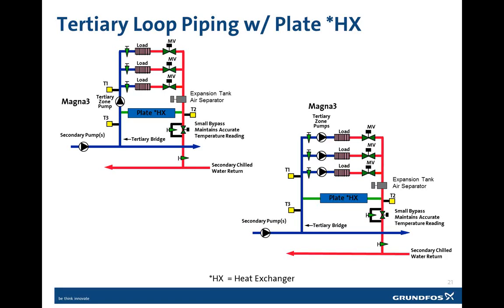So a plate heat exchanger acts as a pressure isolator. If you consider a multiple building campus with a central plant, there could be blocks or miles from the first takeoff all the way out to the farther zone. The near building may be a one-story multi-office building, which requires about 20 feet of head to serve the highest valve and coil, where further downstream could be a 25-story hospital structure requiring 90 feet of head to serve its farthest load. Why should the multi-office building and all of the others be subjected to the pressure that's required to serve the hospital downstream? Really they shouldn't, and that's where the plate heat exchanger comes in, because it eliminates that additional head requirement in the early buildings. So once again, this is a simplified connection of the plate heat exchanger to show for this application.